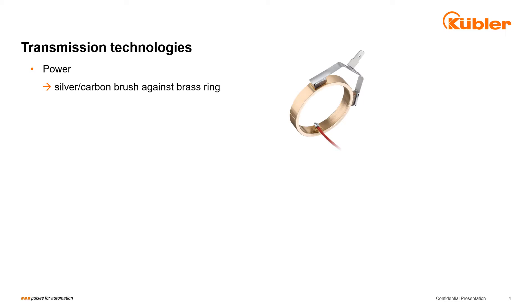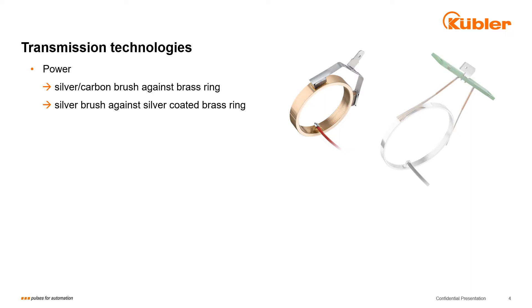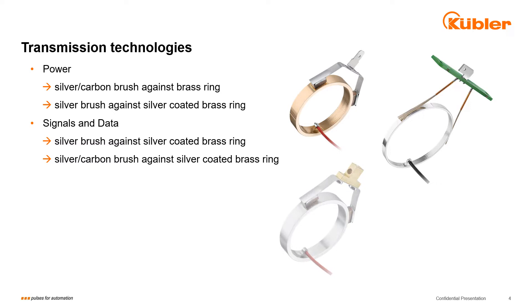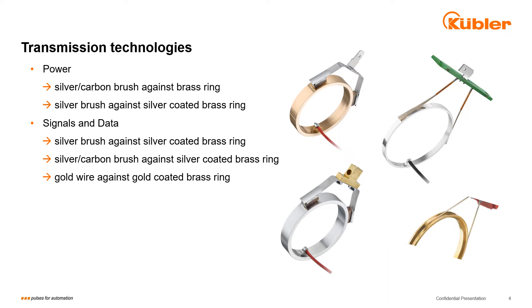Here is a first rough overview of our transmission technologies; details will follow later. For load we usually use silver graphite versus a brass ring, or silver brushes against silver-plated rings. The silver brush against silver ring is also used for signals and data. On smaller slip rings we also use silver carbon against silver ring for signals and data. On top, gold wire technology still has its field of application for transmission in smaller slip rings.